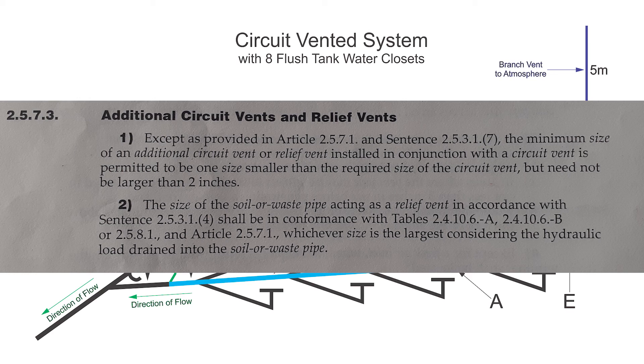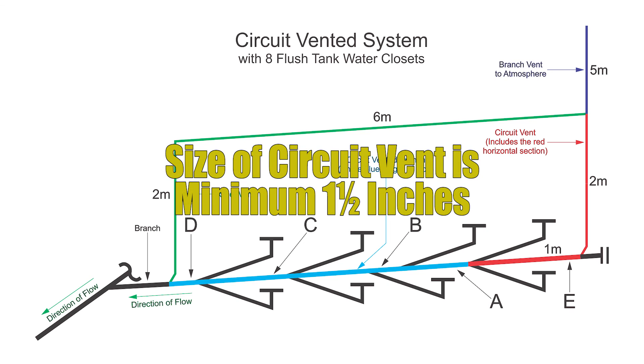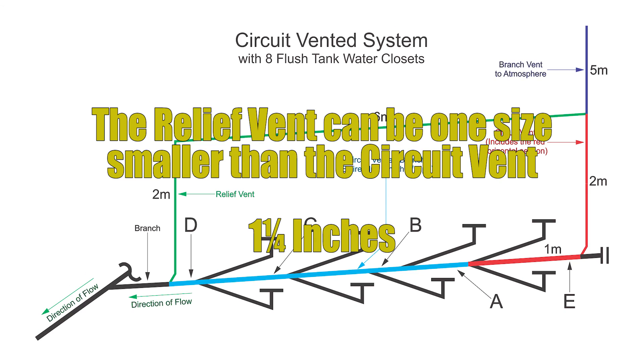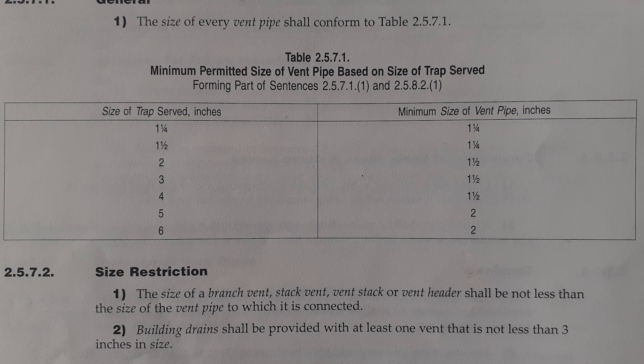Except as provided in article 2-5-7-1 and sentence 2-5-3-1-7, the minimum size of an additional circuit vent or relief vent installed in conjunction with a circuit vent is permitted to be one size smaller than the required size of the circuit vent, but need not be larger than 2 inches. We've determined our circuit vent is 1-and-a-half inches, so one size smaller would be 1-and-a-quarter inches. But this clause also directs us to reference clause 2-5-7-1, which tells us to look at table 2-5-7-1.